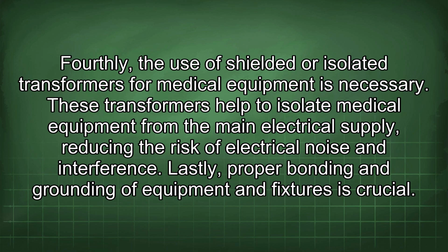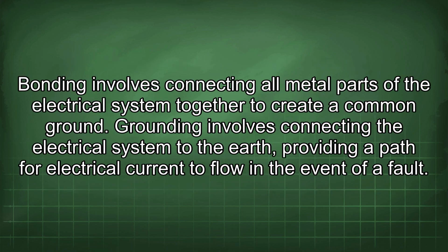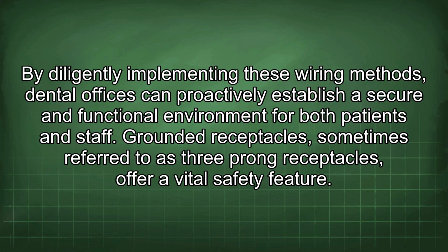Fourthly, the use of shielded or isolated transformers for medical equipment is necessary. These transformers help to isolate medical equipment from the main electrical supply, reducing the risk of electrical noise and interference. Lastly, proper bonding and grounding of equipment and fixtures is crucial. Bonding involves connecting all metal parts of the electrical system together to create a common ground. Grounding involves connecting the electrical system to the earth, providing a path for electrical current to flow in the event of a fault. By diligently implementing these wiring methods, dental offices can proactively establish a secure and functional environment for both patients and staff.